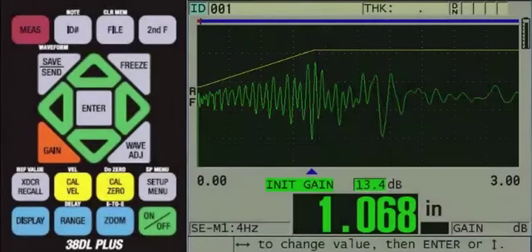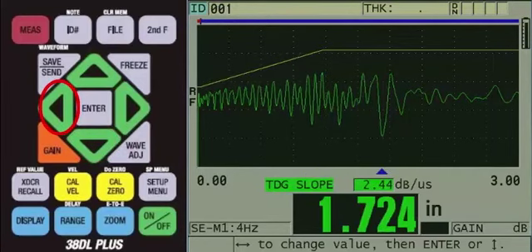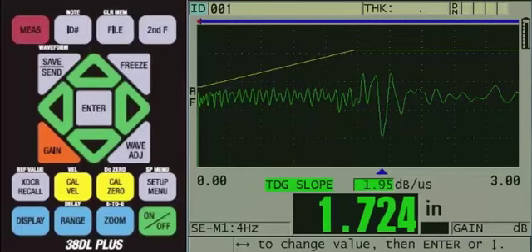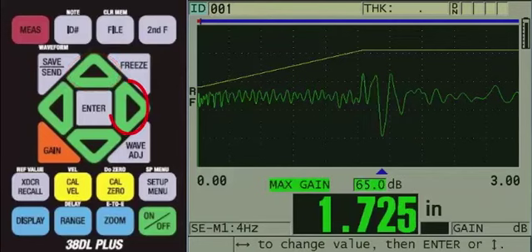Since the majority of internal reflections are under the slanted portion of the gain line, we need to lower the TDG slope. Press the down arrow to TDG slope, then use the left arrow to lower the slope until the gauge stops detecting the internal reflections and instead detects the true back wall echo. Lastly, we will make a slight adjustment to the max gain. Press the up arrow twice to max gain, then use the right arrow to increase the max gain slightly to further amplify the true back wall echo. The gauge is now detecting the true back wall echo, and the signal is strong in amplitude.